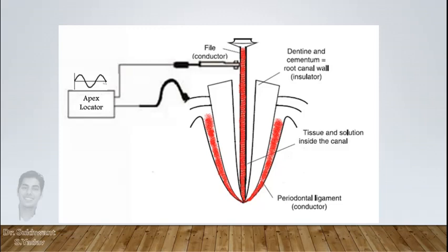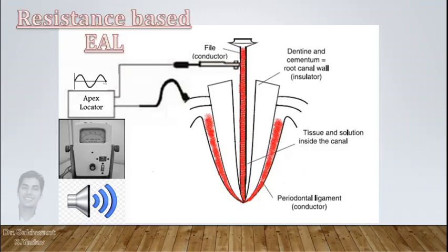As this resistance is equal to the resistance at lip clip which is placed on oral mucosa, a beep sound is generated. That indicates apex. Then reduce 0.5 mm from this length and that will be final working length. This is the principle of first generation apex locators.